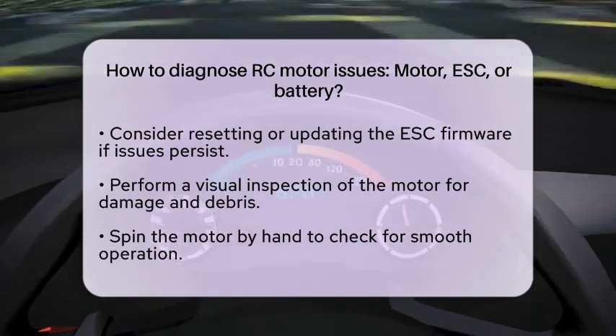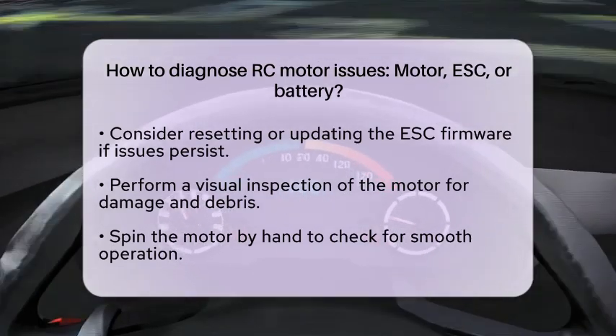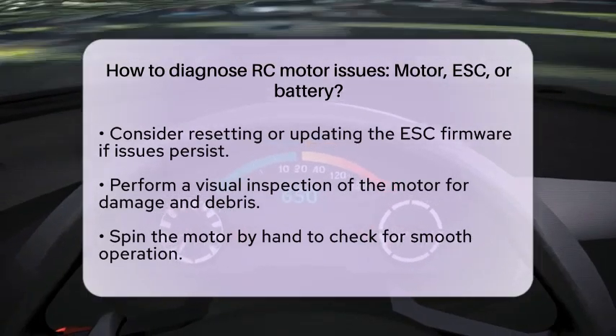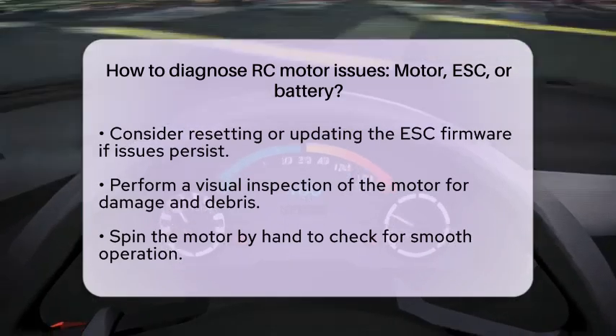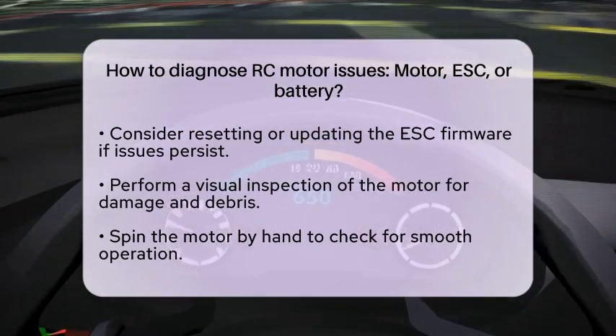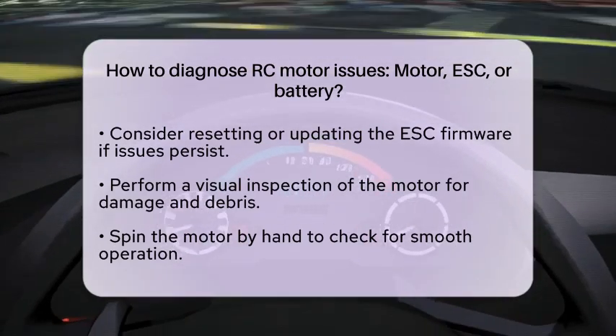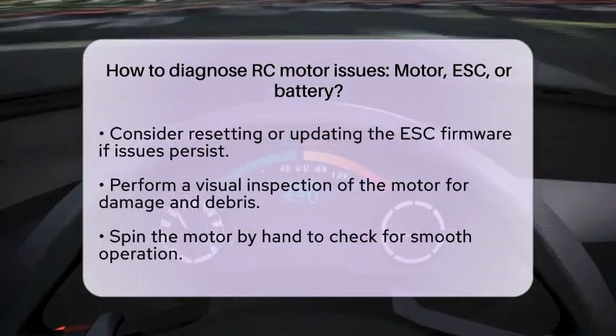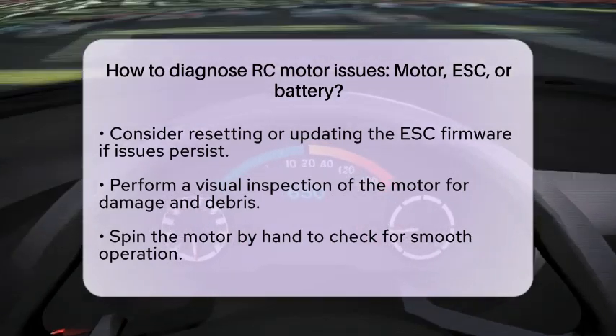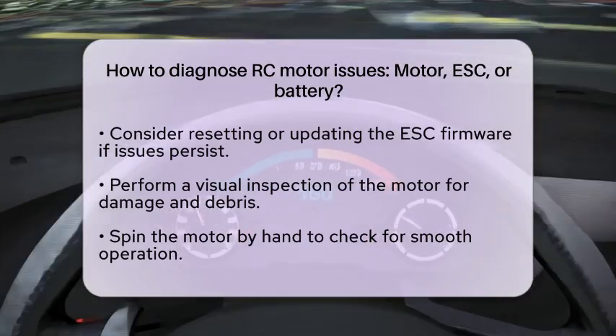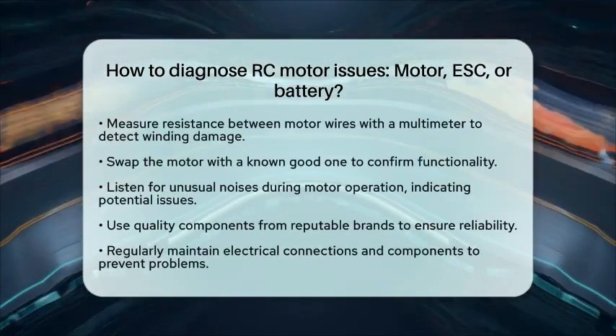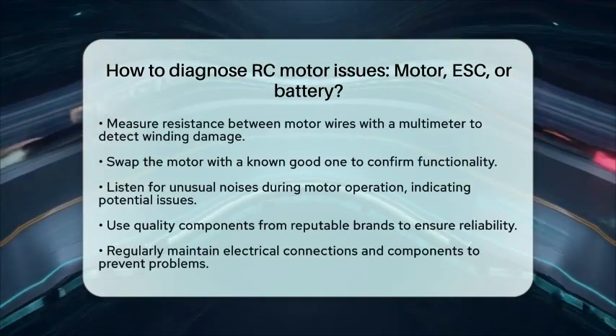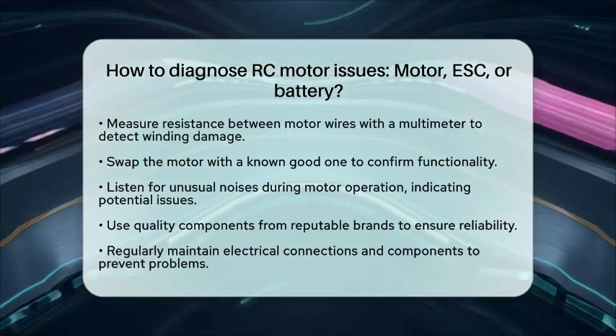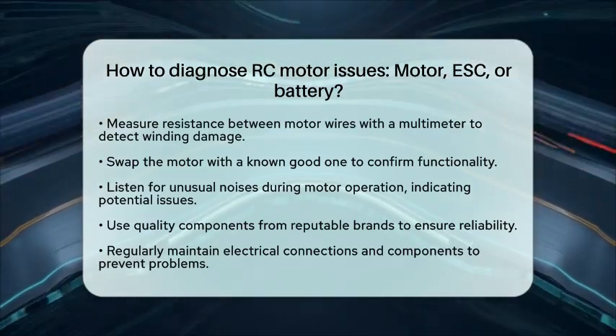Using a multimeter, measure the resistance between the motor wires. Significant imbalance or open circuits indicate winding damage. If possible, swap the motor with a known good one. If the replacement motor runs fine, the original motor is likely defective. Listen for any unusual noises during operation. Grinding, clicking, or irregular sounds suggest mechanical or electrical issues with the motor.